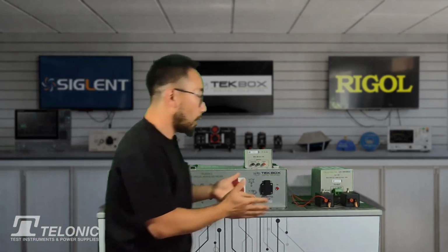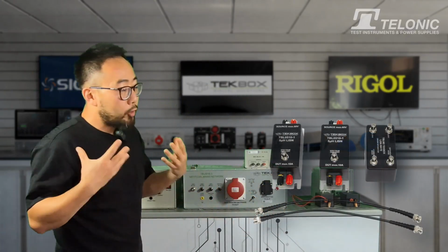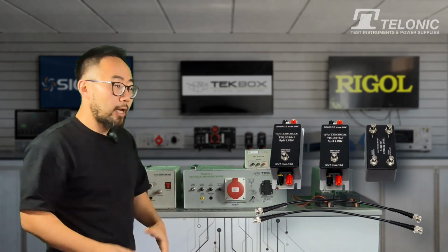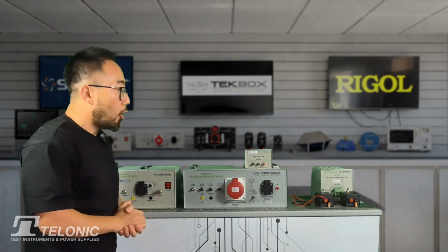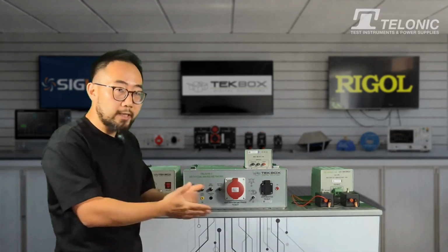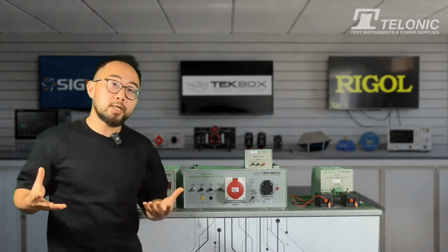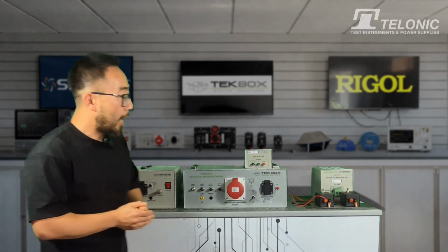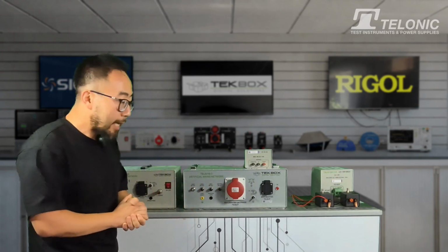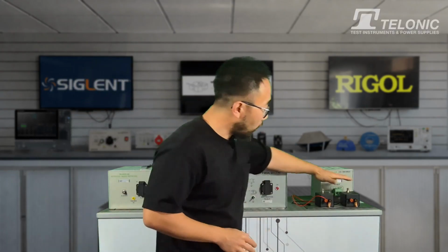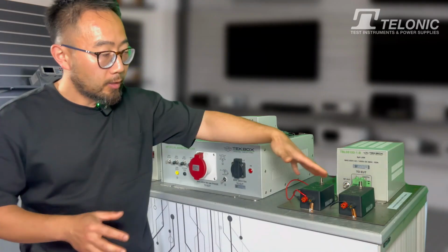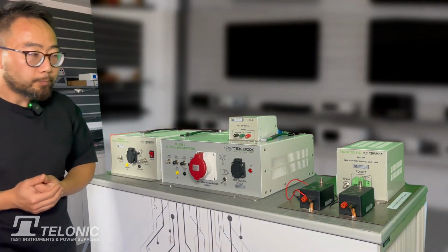Now we move to DC types of LISN. Typically speaking, we use DC types of LISN for applications such as military defense, such as MIL standards, DEF standards, or automotive standards. Nowadays, there are many companies specializing in making products for space and satellite applications. We also use DC power. And if you go through the standards I just mentioned, they always use two LISNs. So that's why you can see here, these two LISNs are set up according to the standards.